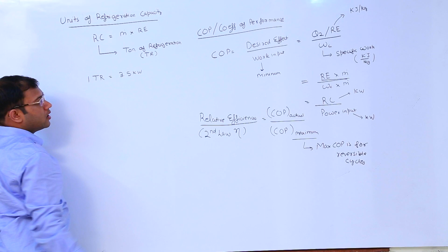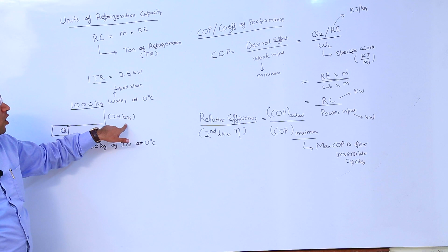Suppose there is 1000 kg of water in liquid state at 0 degree Celsius. Now I need to convert it into 1000 kg of ice at 0 degree Celsius, and that too in 24 hours. So I need to absorb some heat from water at 0 degree Celsius, then only it will solidify. It is a phase change process. This amount of heat absorbed from 1000 kg of water to convert it into 1000 kg of ice at 0 degree Celsius in 24 hours is nothing but your ton of refrigeration. 1 TR comes out to be 210 kilojoule per minute or 3.5 kilojoule per second, known as 3.5 kilowatt.